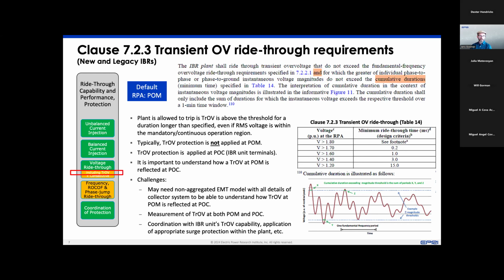Some of the challenges, however, and you heard that before, is that one would need a non-aggregated EMT model to really study the transient overvoltage exposure of the units in the plant, and the measurements would have to be taken at the plant and the unit level. And the equipment for those high resolution measurements in the transient time frame might be limited, or at least come with some specific costs. So the whole question of conformity assessment of the plant without adequate measurements can be a challenge.